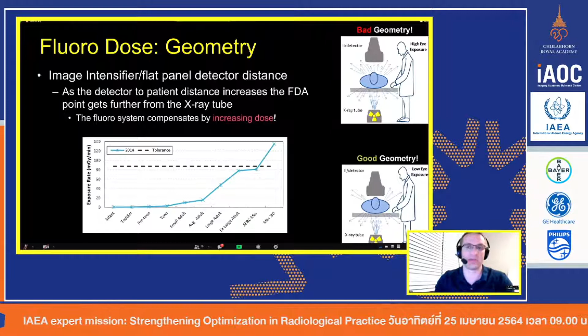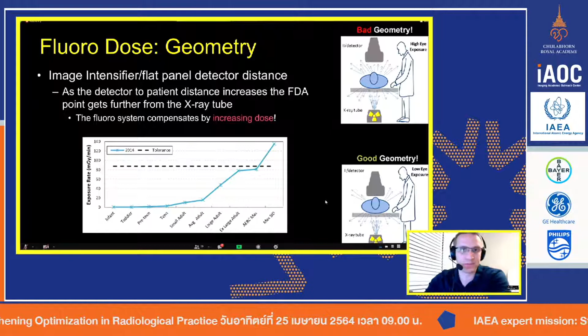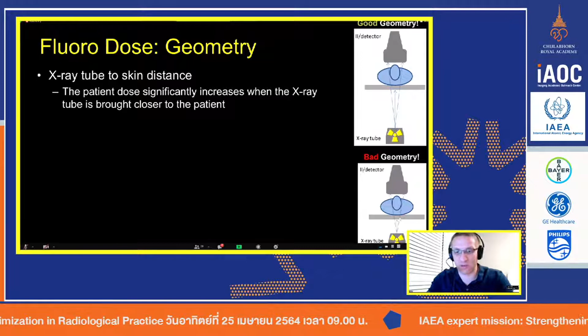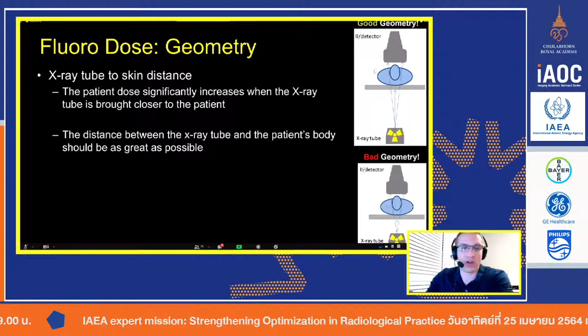I recognize that sometimes it just has to be where it has to be. But in the best case scenario, you should keep it as close to the patient as possible. Now, we talked a little bit about having the patient as far away from the X-ray tube as possible. This obviously depends a lot on how high you can set the table, and the operator can use it comfortably. If you have a short operator, the table is going to be lower, and therefore the patient is going to be closer to the X-ray tube. That's just something that you have to deal with. In a best case scenario, push it as far away as you can, and it just reduces the dose to the patient. In some situations, you can actually manipulate where the X-ray tube is.